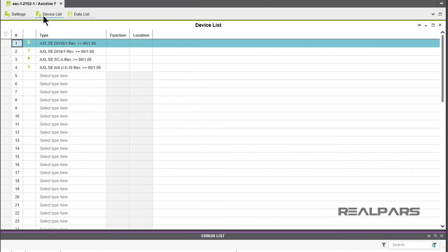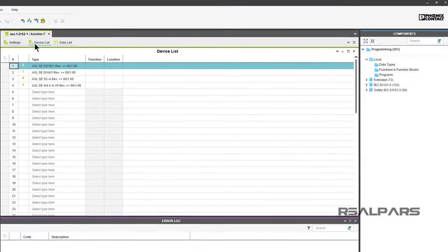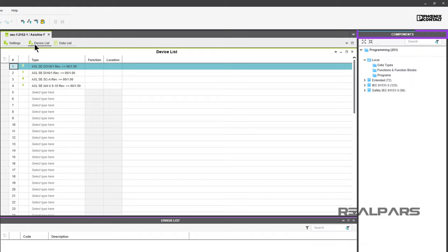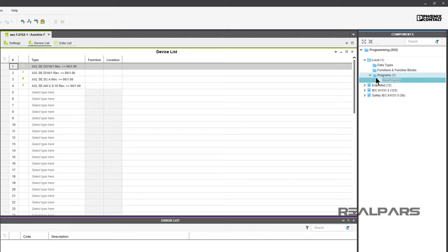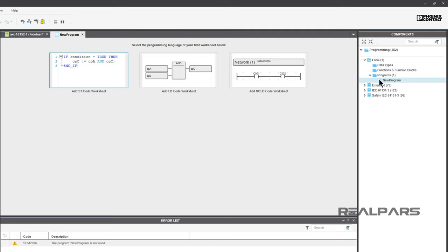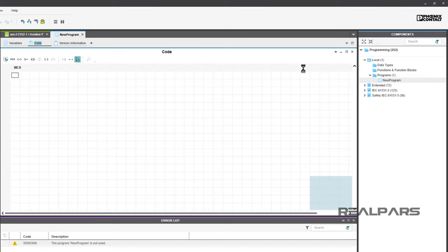Here's how it works. We need to tell PLCnext Engineer that we want to start a new program using ladder logic. Under the Components column, right-click on Programs, then choose Add Program. The default name for your program is New Program. That name can be changed at any time. Double-click on New Program and choose the ladder logic program Network 1. A clear ladder logic sheet will open under the header code.